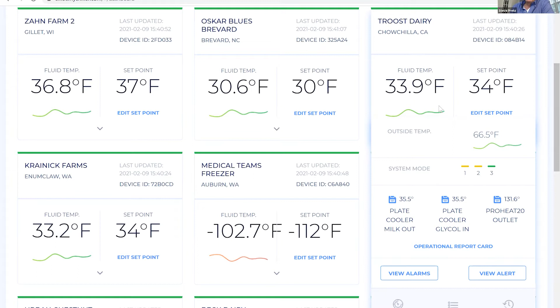If you've got poor ventilation around your chiller, poor airflow, maybe the chiller is indoors, which is common in a lot of our smaller brewery applications. This tells us the environment the chiller's in. This is probably pretty close to what the temperature is in California right now. We're showing about 66 degrees. System mode, we're showing this dairy's basically operating on one unit, number 3 right now, and units 1 and 2 are in standby mode.